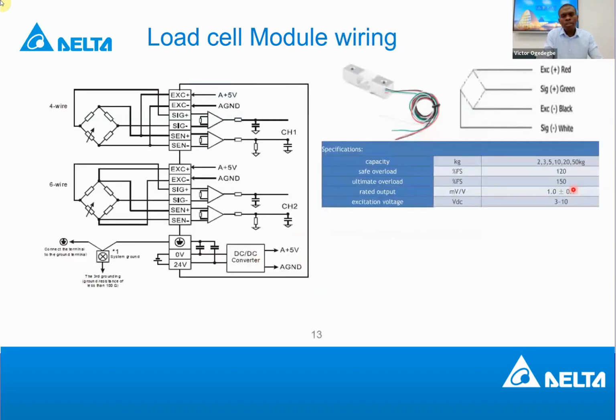So let's proceed. This is the wiring. To wire the load cell to a load cell module is very easy. What happens is that when you buy a load sensor, depending on the name you call it, the cables on those load cells are labeled. So each cable corresponds to a signal. Like this very load cell here, it has a red cable. The red cable is the positive excitation voltage. This is the voltage that the load cell module supplies to the load sensor. The black is the ground. So you connect the red to the red and the black to the black.